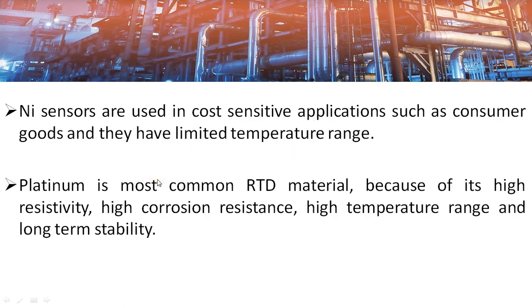Out of all the metals, platinum is the most widely used RTD material because of its many advantages: high resistivity (that is, change in resistance per unit temperature variation is high), high corrosion resistance which improves the life of the RTD sensor, high temperature range, and good long-term stability.